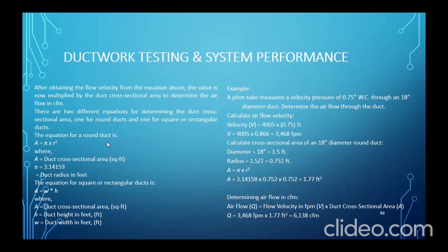So the equation for a round duct is A = pi r squared, where A is the duct cross-sectional area, pi, siyempre, is 3.14159 o yung pi sa calculator niyo, and r is the duct radius in feet. The equation for a square or rectangular duct is A = W times H, where A is the duct cross-sectional area, H is the duct height in feet, and W is the duct width in feet.